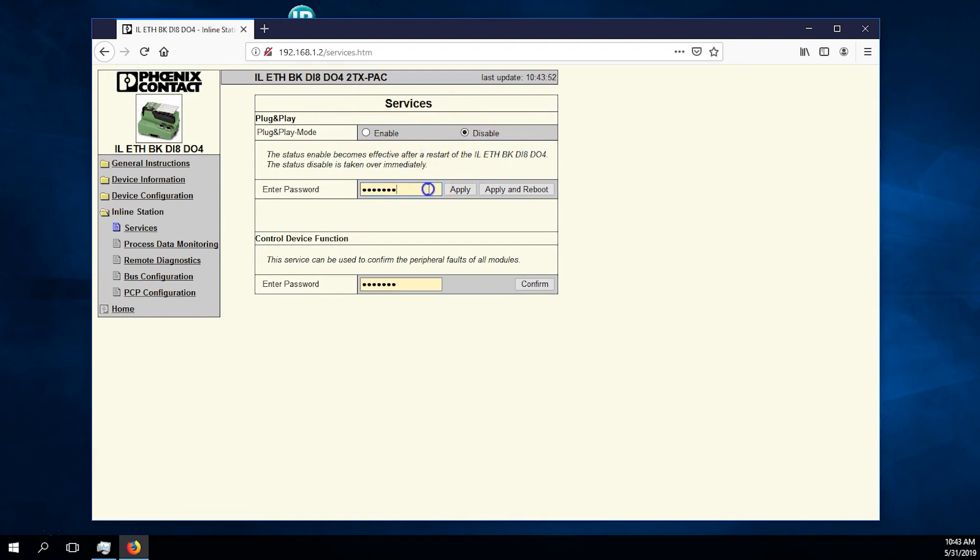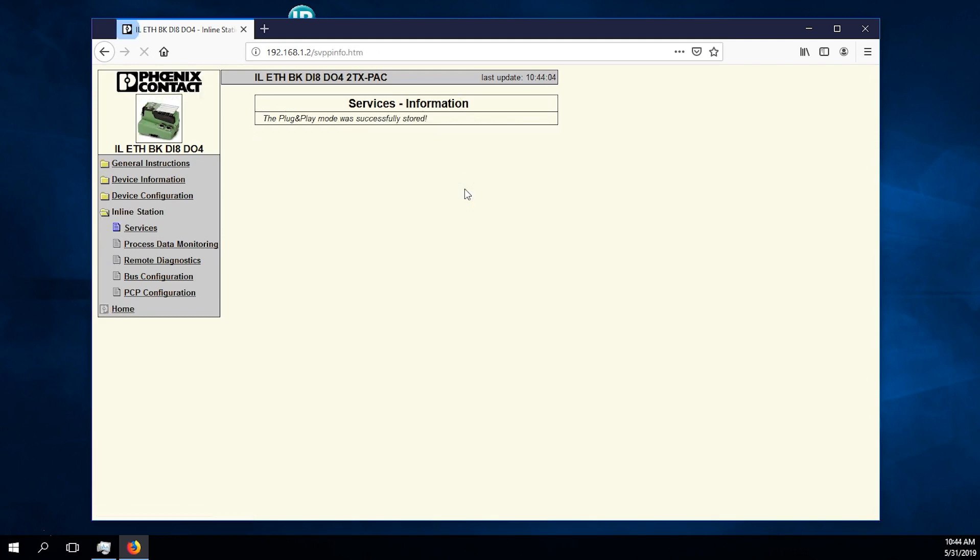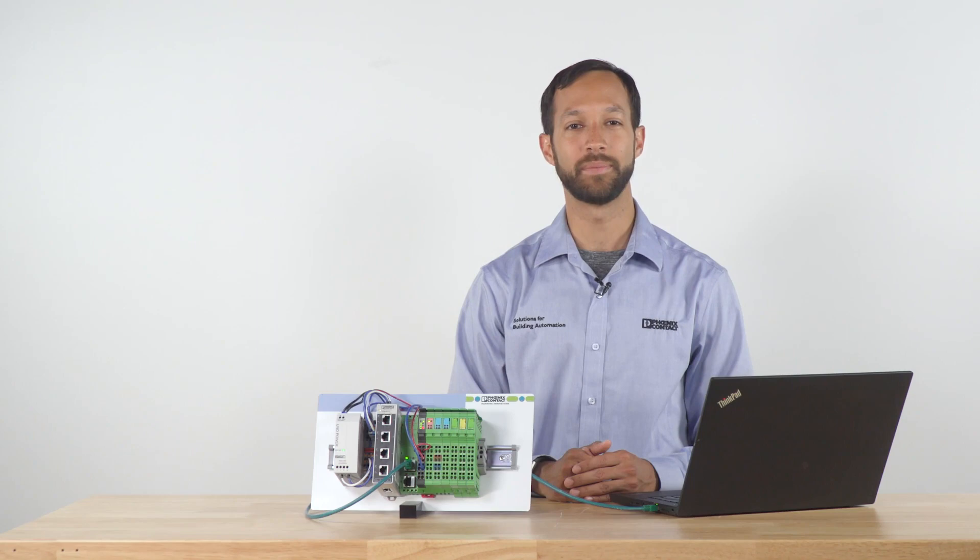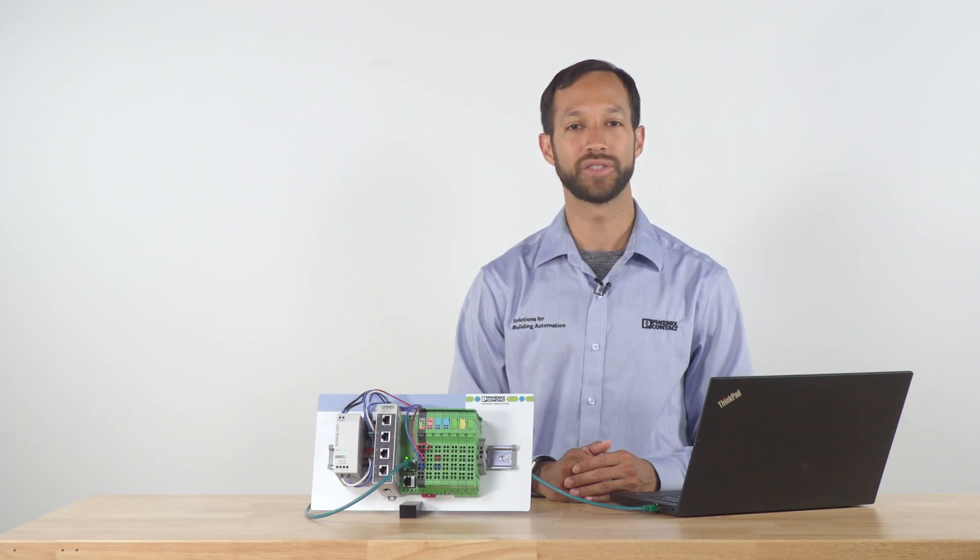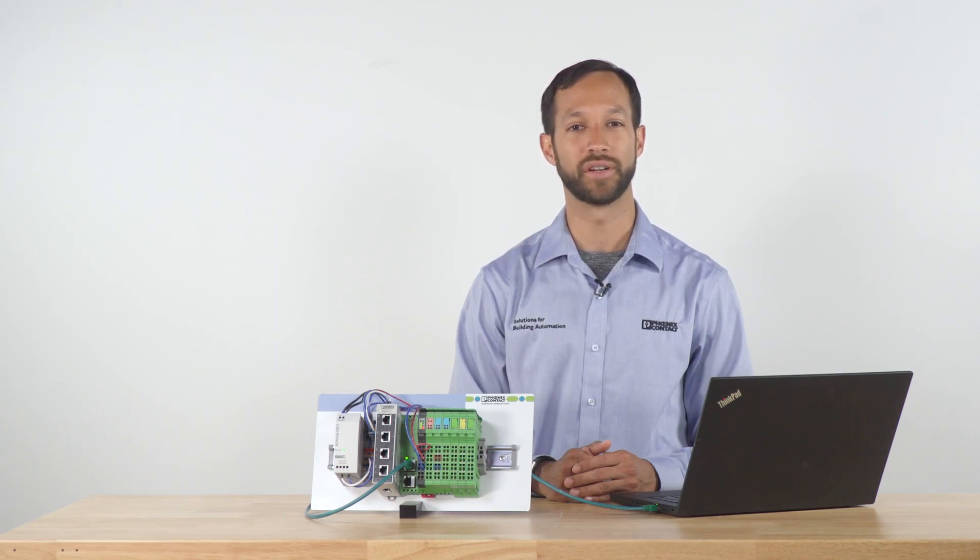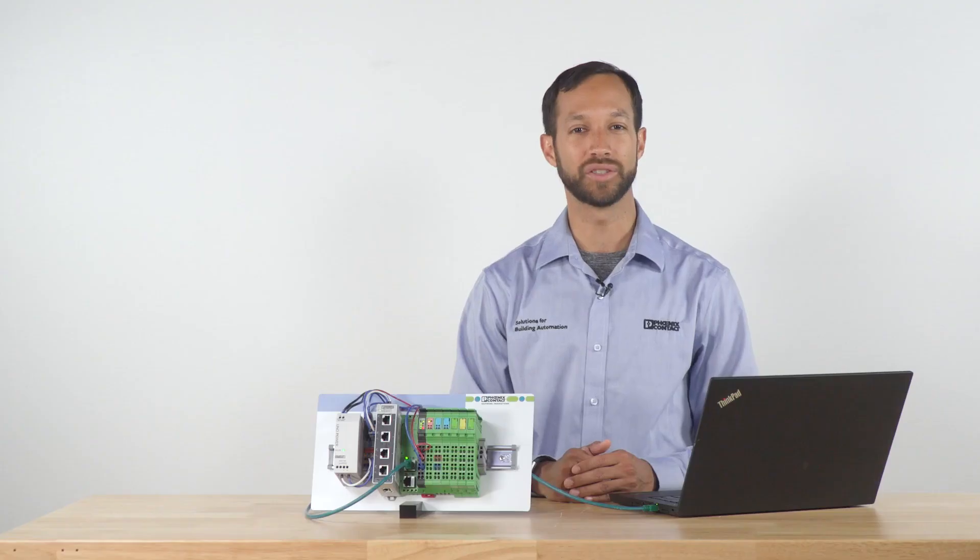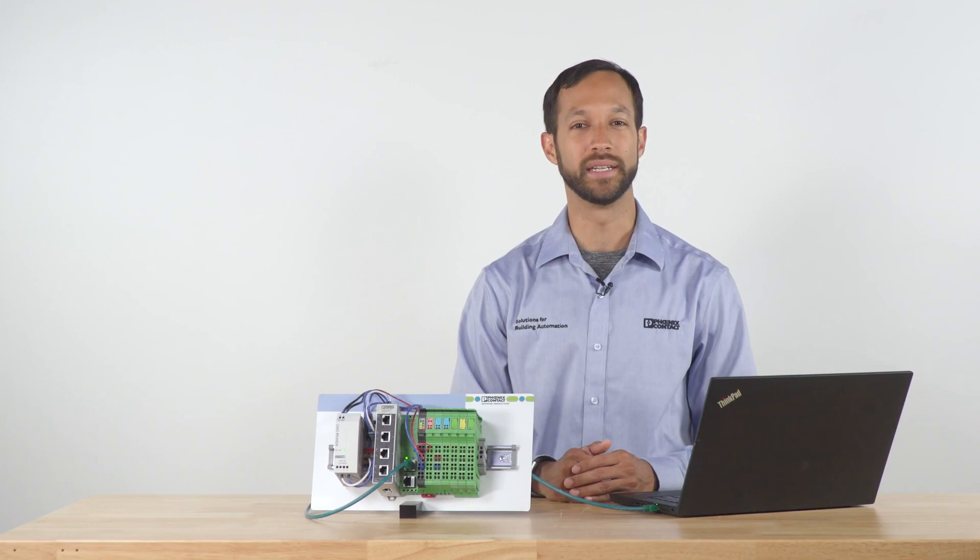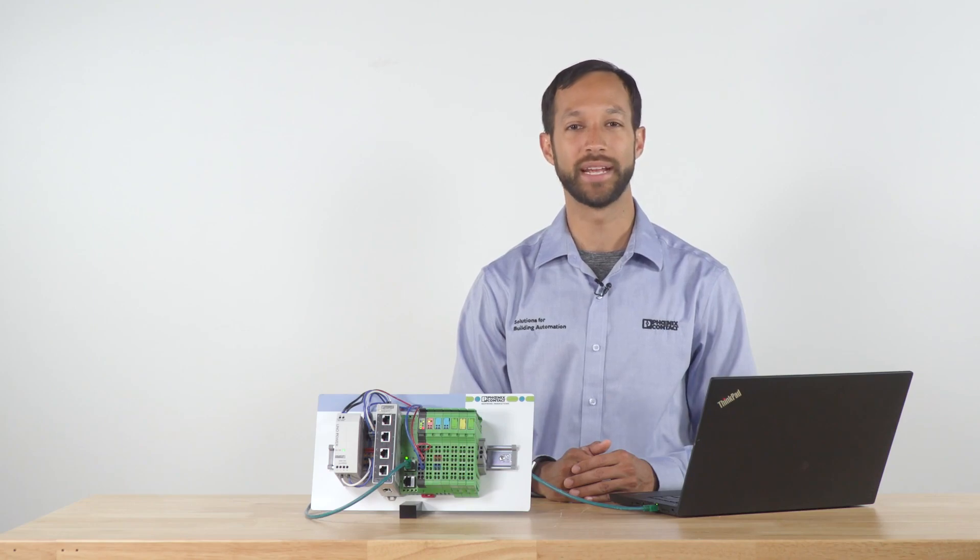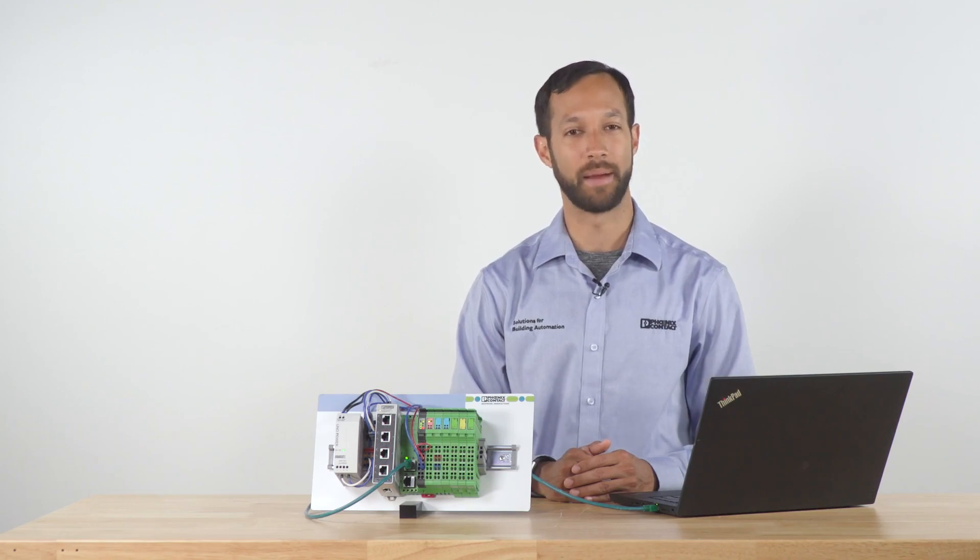Plug and play mode is used for the head station to create a mapping of the connected I.O. To go into operation, this mode needs to be turned off so the I.O. station can lock in the current configuration for diagnostics and Modbus TCP mapping purposes. If the physical I.O. is changed, this mode will need to be re-enabled and the I.O. station rebooted to recreate the Modbus mapping.